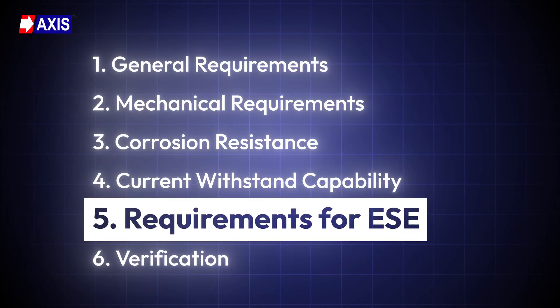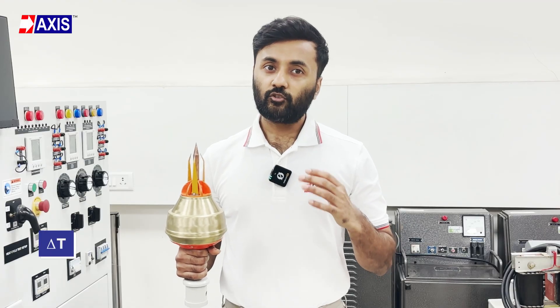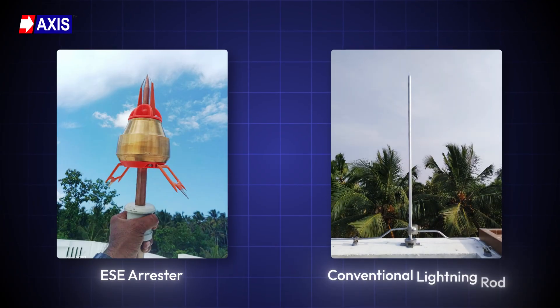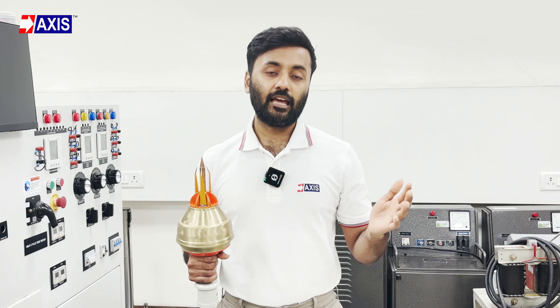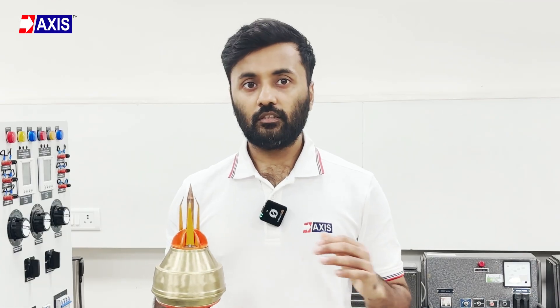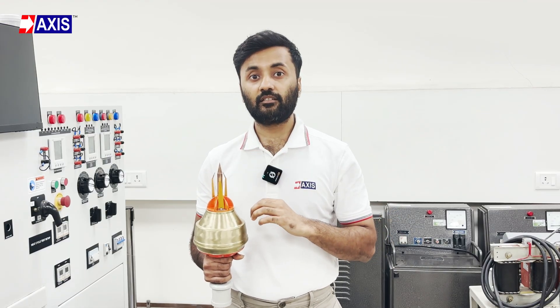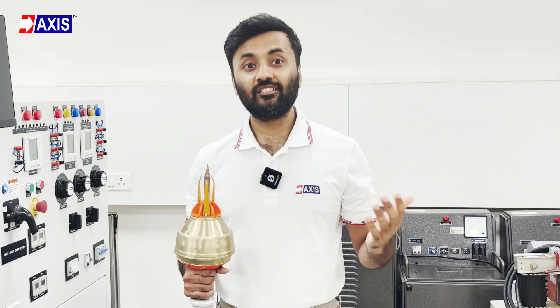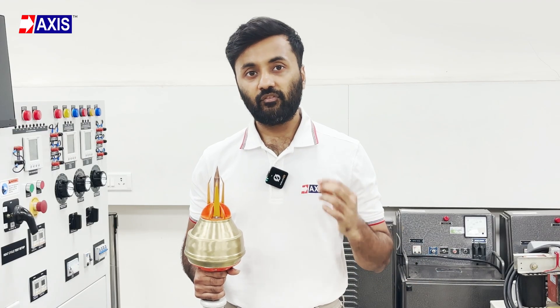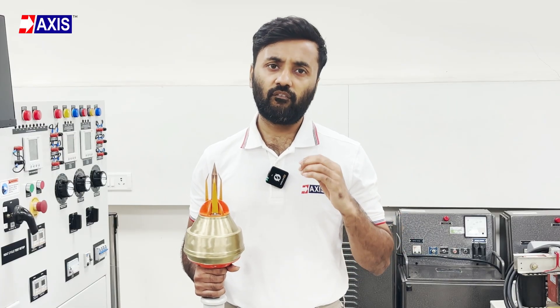Fifth, requirements for ESE: the early streamer emission is measured as a time difference called delta T. It shows how early the ESE arrester responds compared to a conventional lightning rod under the same conditions. Delta T must fall between 10 and 60 microseconds. If it is below 10, the device is not considered an ESE arrester. If it is above 60, the value is capped at 60 microseconds for all protection calculations. A higher delta T means the arrester reacts earlier and protects a wider area. The components that capture the lightning strike — mainly the tip of the lightning arrester — must meet size and finish requirements given in NFC 17-102. The striking point must be made from solid metal with a smooth continuous surface. If it has a coating, the minimum thickness must be 50 microns and it must be free of defects like cracks or tarnishing.